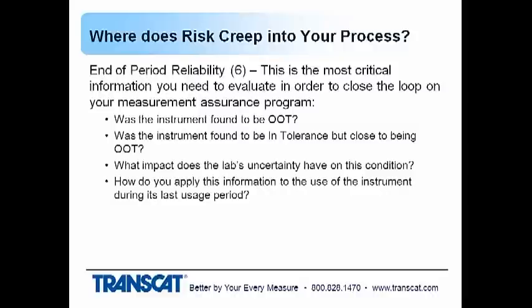End of period reliability is the most critical information you can have, because now that you've used it for that calibration interval in your process to make decisions about your product, here's the final result that tells you how it performed, how that instrument performed, whether it maintained its tolerances. Was it found to be out of tolerance, or was it in tolerance and close to the out of tolerance limit, which can still have an impact on your decisions about the quantitative values that it provided. And then this gets into the lab's measurement uncertainty, and how this impacts that close to being out of tolerance region. How do you use this information to determine how it affected your product or your decisions about the product or tests that you ran during the last calibration period?